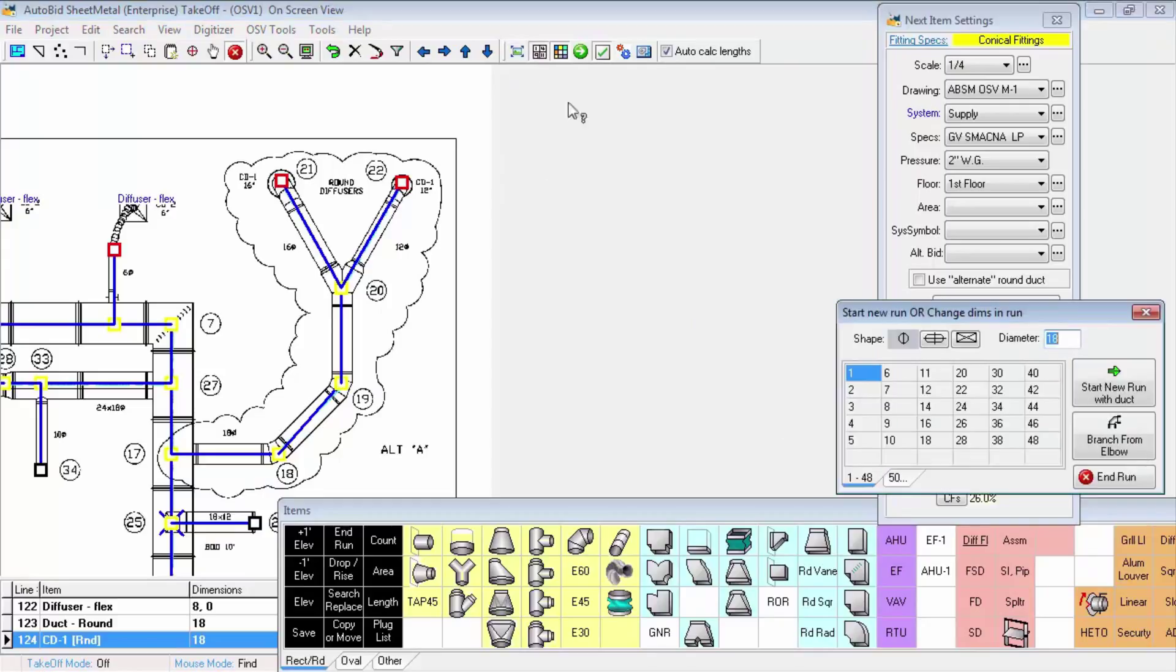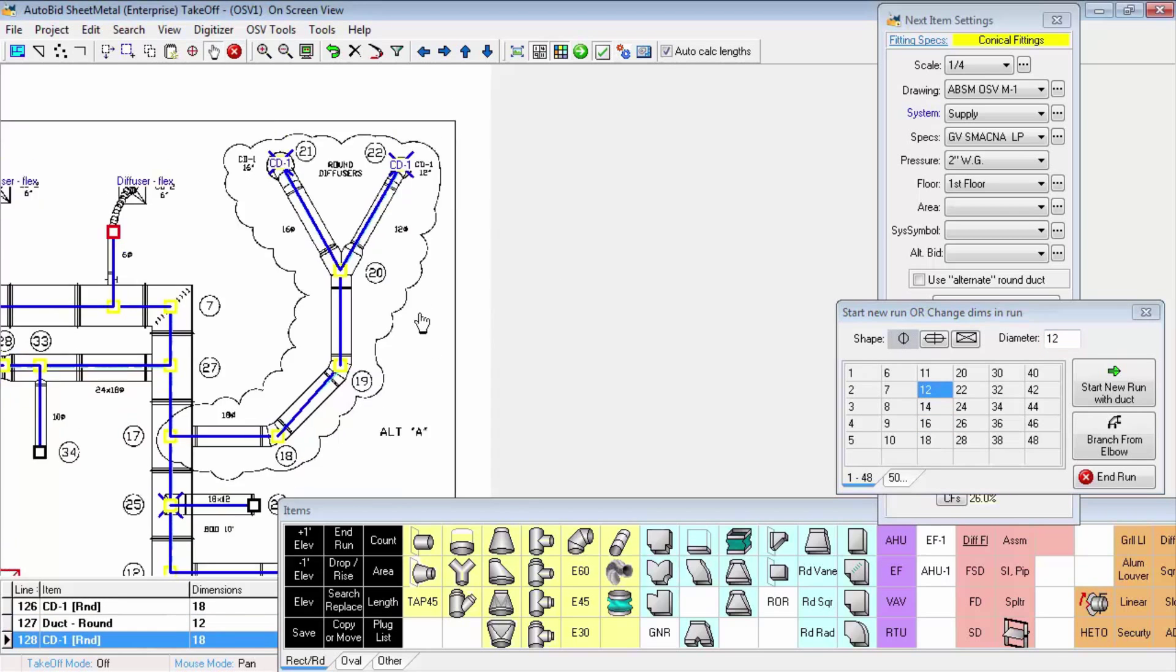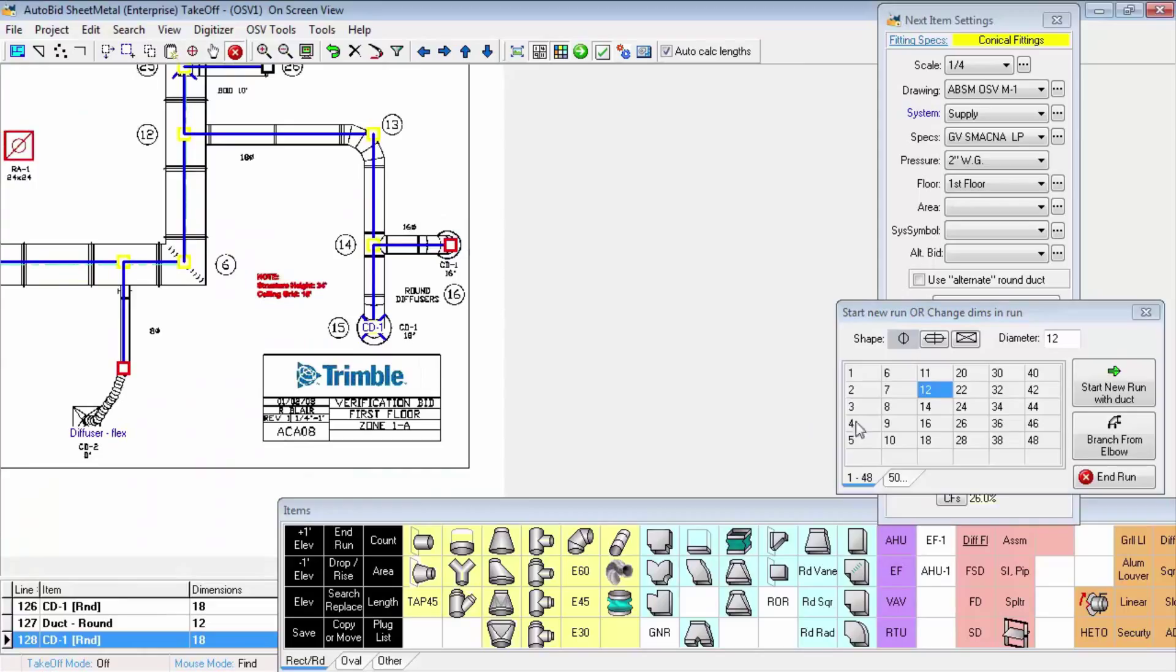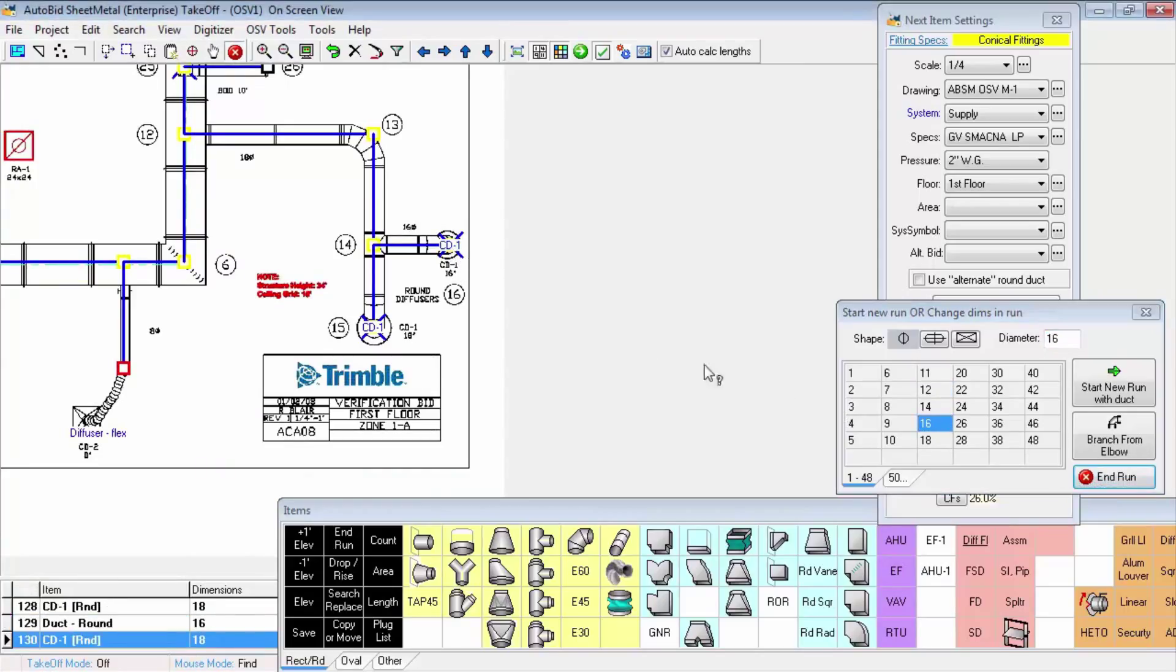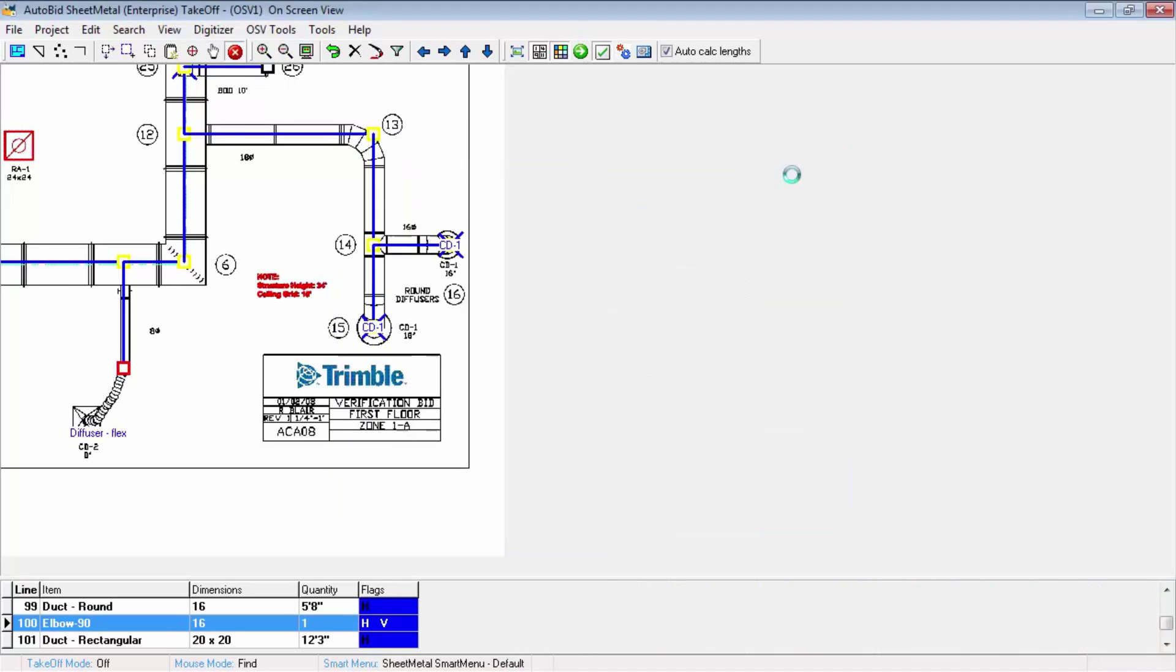Then we go around and search the drawing for any other places we need drops down to a similar symbol. In this case, we're going to bring in a 16-inch drop, a 12-inch diameter drop, and another 16. The Xs on the screen represent a vertical window. If we take a look at that vertical window, you'll see we've got an elbow at the top, and there's our symbol ceiling diffuser at the bottom with four feet of duct between them.